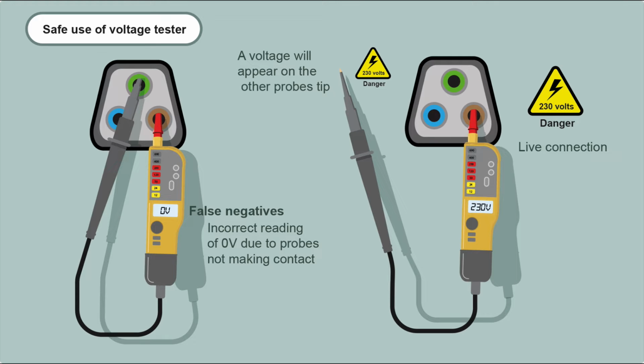I'm just going to quickly go through a few possible issues when you're using your voltage tester. These socket adapters that you can plug into a socket so you can put your tester in, you often find that the probes won't work with these. You put your probes in and you're getting 0 volts. That's because the probes aren't making a connection inside the adapter. Normally you can pull the tip off the lead and you actually put the lead into the adapter. I've got a little video of this in a bit.